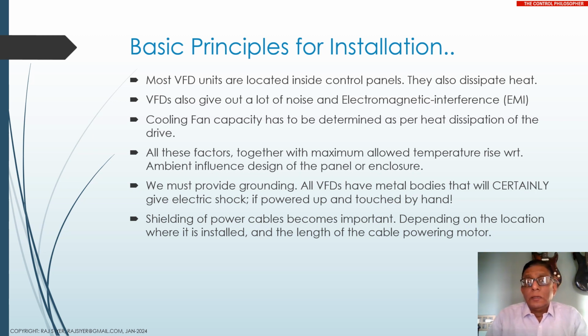Then the cables that are powering the VFD and also the cable powering the motor must be shielded or screened. Okay, in India we don't particularly use screen power cables, but we use armored cables, which are very good. They are as good as screen cables. But only condition is that the armored cable should use proper metal glands which must be correctly grounded without compromise.